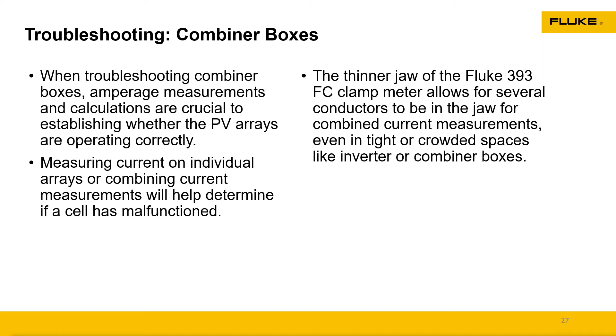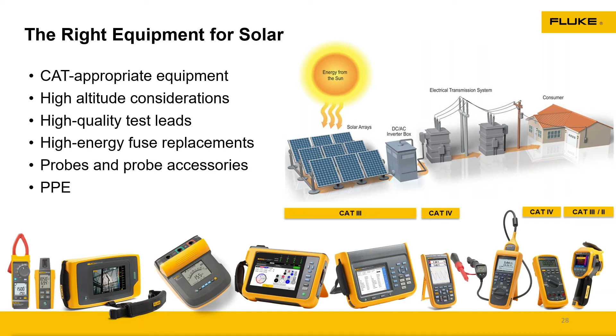As I mentioned before, make sure that your tools are category rated for these environments. If you're out working on solar panels, that is considered a category 3 environment. Know your category rating and make sure the tool that you have is appropriate for that job. This is a great illustration because you can see the solar panels are Cat 3, going through the inverter is Cat 3. As soon as I go outside that inverter and start getting back onto the utility, that is considered a category 4 environment. And then once we go out of our utility back into consumption, it goes back into that Cat 3 and Cat 2. So know your meters, know what tools you need.